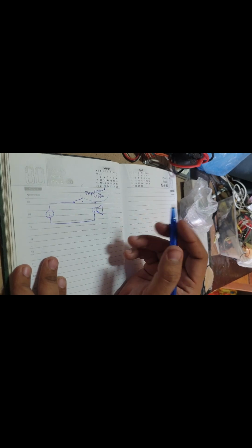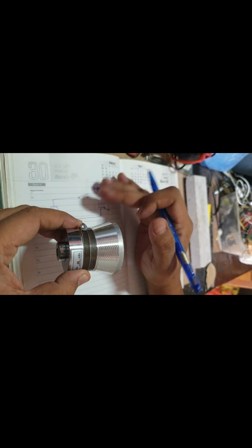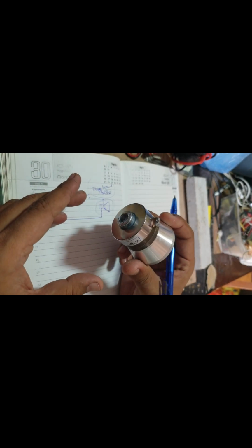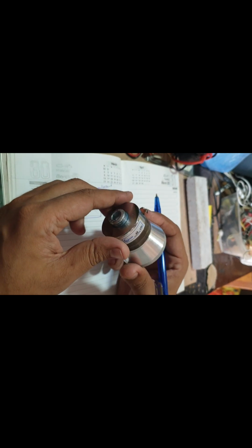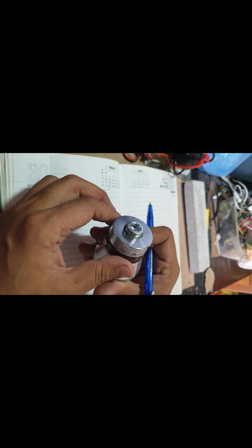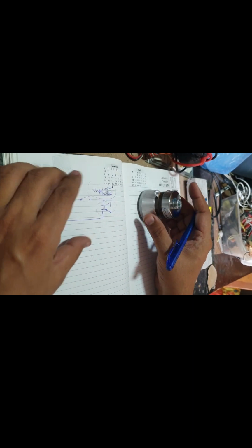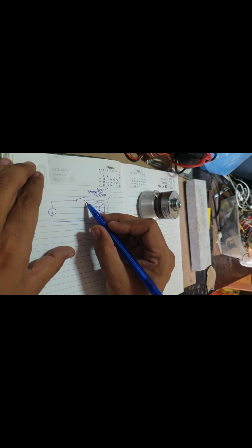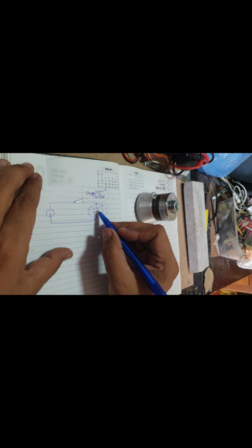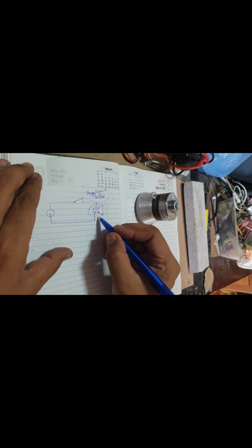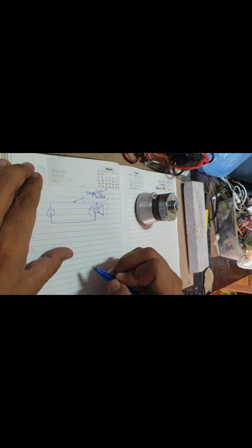Okay, so but this will not drive, this will not create the resonance in the transducer. These transducers work differently. If we tap it 3 times, it will not create a resonance in this transducer. The reason is that they are like a capacitor, 2 plates parallel to each other, so they will store the charge. So even if we tap it, it will not create the resonance because of the charge.